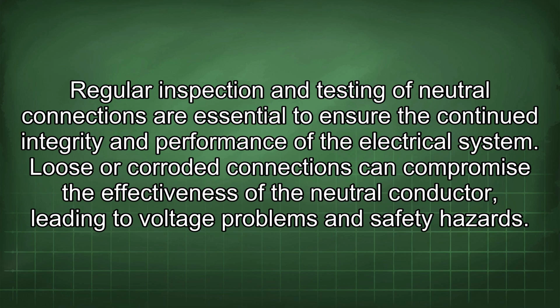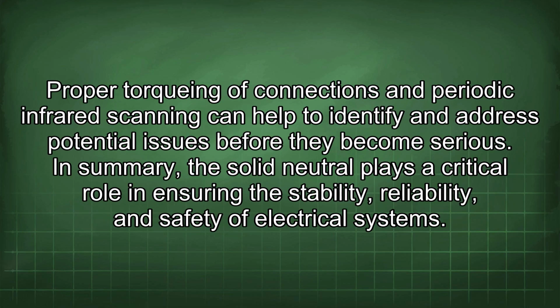Regular inspection and testing of neutral connections are essential to ensure the continued integrity and performance of the electrical system. Loose or corroded connections can compromise the effectiveness of the neutral conductor, leading to voltage problems and safety hazards. Proper torquing of connections and periodic infrared scanning can help to identify and address potential issues before they become serious.